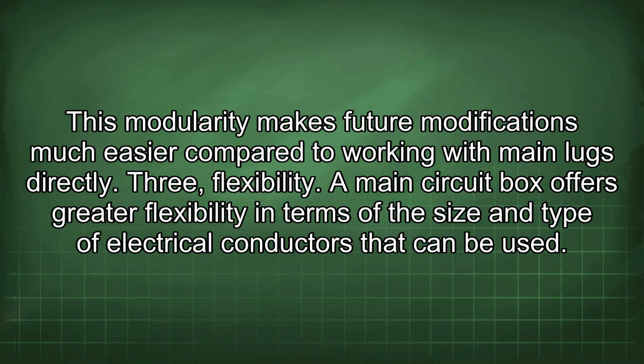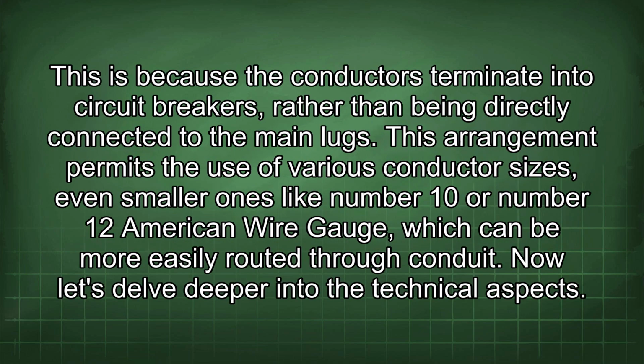3. Flexibility. A main circuit box offers greater flexibility in terms of the size and type of electrical conductors that can be used. This is because the conductors terminate into circuit breakers rather than being directly connected to the main lugs. This arrangement permits the use of various conductor sizes, even smaller ones like number 10 or number 12 American wire gauge, which can be more easily routed through conduit.